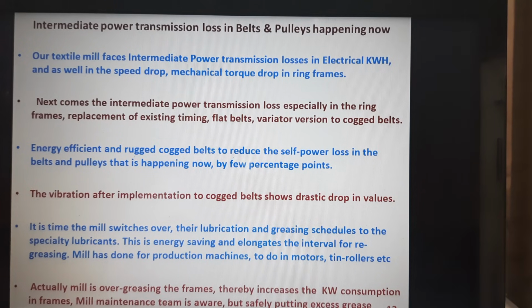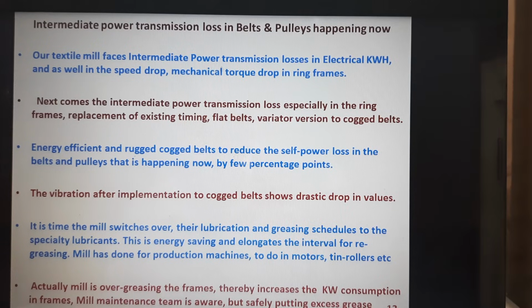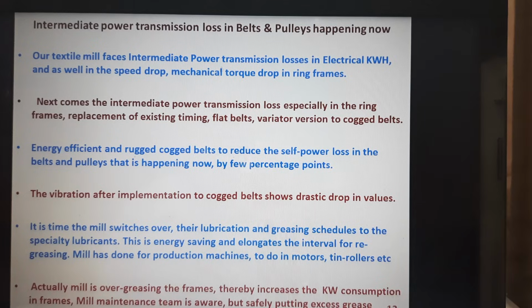More than everything else, for the vibration and predictive monitoring of any machine, especially the ring frame, after doing this conversion, once the vibration is studied, you find the vibration has dropped drastically. Coming to the lubrication of all the motors in the mills, the mill has taken an excellent lubrication schedule for all their production machines, but all their motors are still lubricated with multi-purpose grease only. This can be changed to specialty lubricants like polyurea thickened mineral complex grease, where even the imported or MNC motors also suggest a 3-year greasing interval. That definitely gives an energy saving and a smooth running of the motor, and the heat dissipation is there from the bearing end to the motor skin as such.